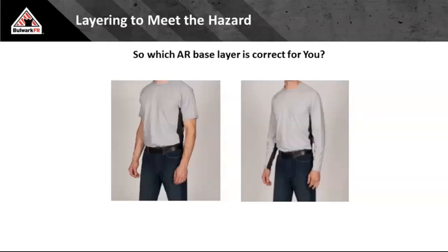Now, if I go to a long sleeve base layer and I test this system as worn, not only am I more protective, now I have more information which I can apply to the energized work I may be doing. For example, this shirt and a 7-ounce outer garment might, when tested, give you 24 calories of protection. I've got 12 calories of protection in my lower half. I have a 15-calorie face shield. I have a 12-calorie balaclava. Assuming all my other PPE, what incident energy can I work on?